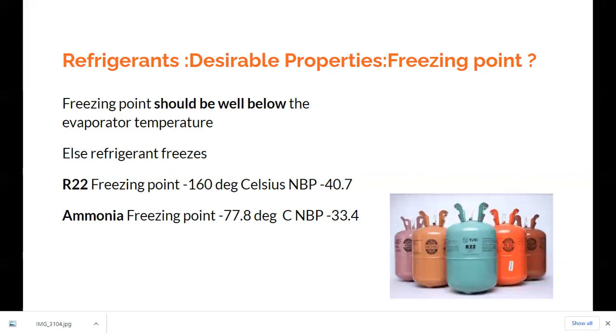The condenser pressure and evaporator pressure are decided again by the normal boiling point. And how are they decided? They are decided because of the temperature range. For example, the evaporator operating at 5 degrees centigrade and the condenser operating at 40 degrees centigrade would have a corresponding saturation pressure of the evaporator and condenser, and that has to be decided by the normal boiling point. So what are the desirable features? One very important thing about evaporator pressure is that it should be slightly above the atmospheric pressure.